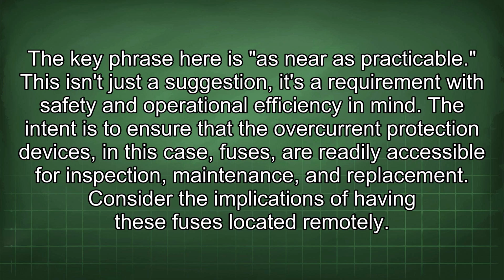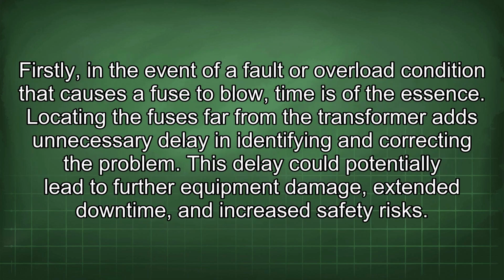The intent is to ensure that the overcurrent protection devices, in this case fuses, are readily accessible for inspection, maintenance, and replacement. Consider the implications of having these fuses located remotely. Firstly, in the event of a fault or overload condition that causes a fuse to blow, time is of the essence. Locating the fuses far from the transformer adds unnecessary delay in identifying and correcting the problem. This delay could potentially lead to further equipment damage, extended downtime, and increased safety risks.